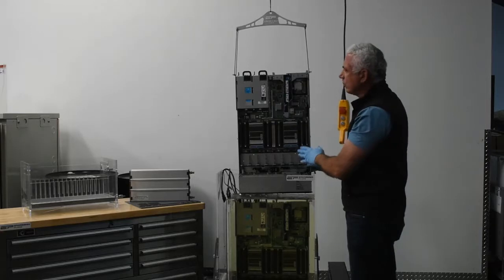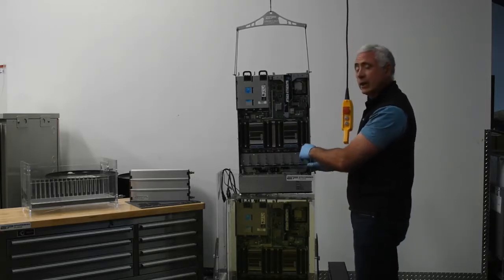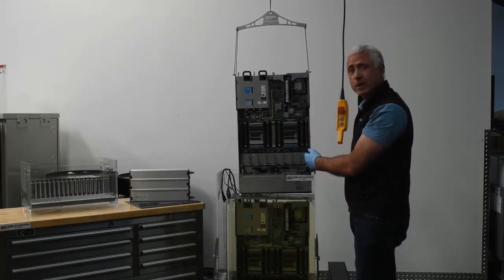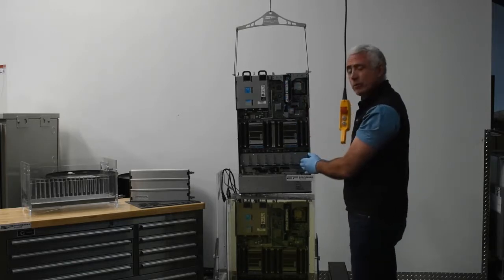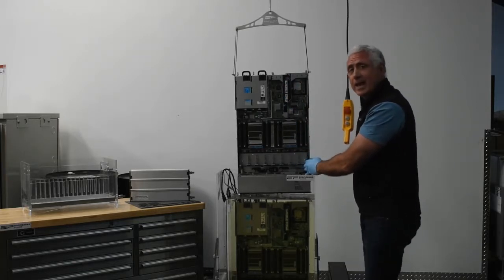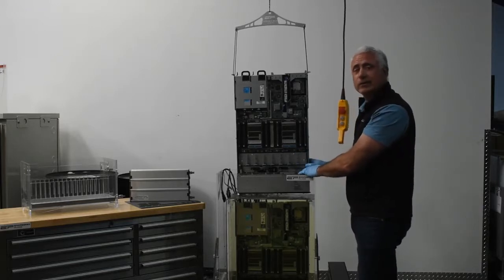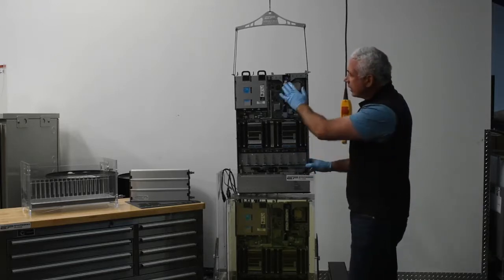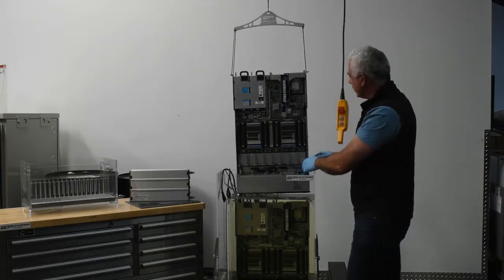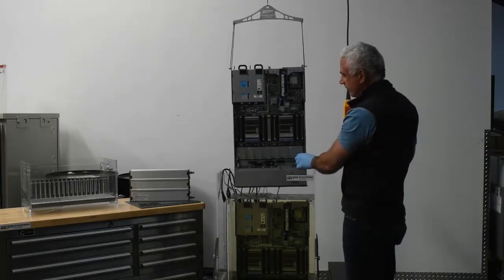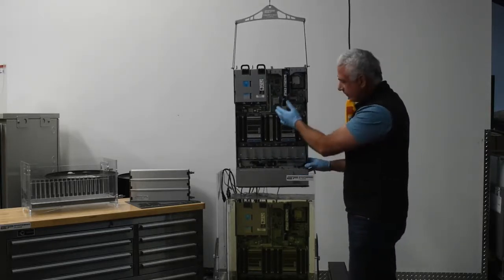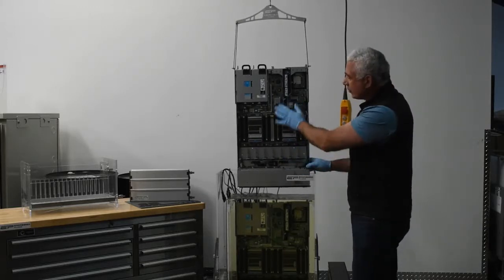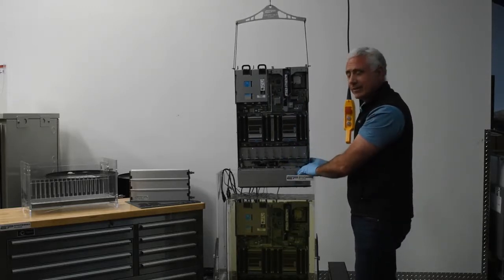The only time you have to remove the fluid is if you were going to say return this server to the manufacturer, in which case you can actually remove it in its entirety. And in a future video we'll show you how to use our dielectric solvent or DS100 to clean all of the fluid off. So you'll see that just by having the server above the tank the fluid drips back into the tank. We want to do that. We want as much of the coolant to remain in the tank.